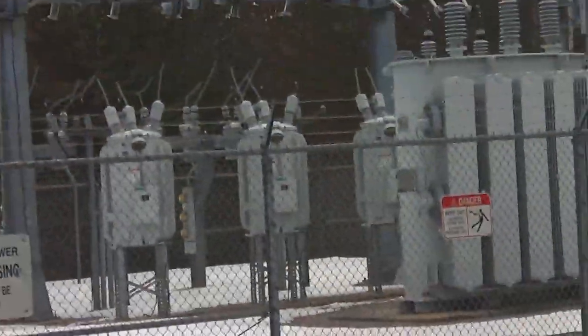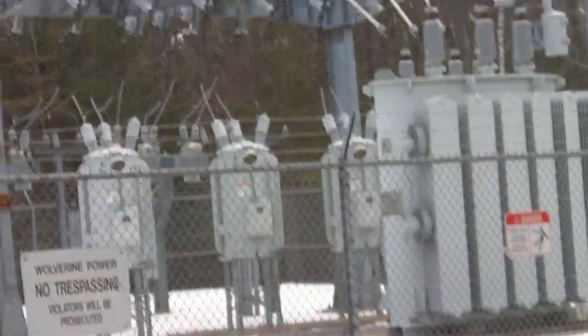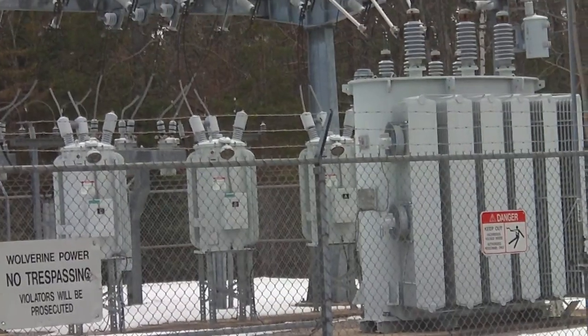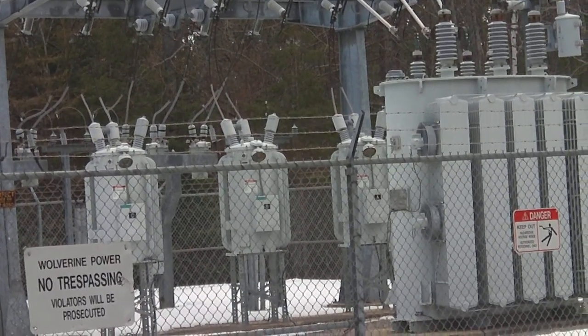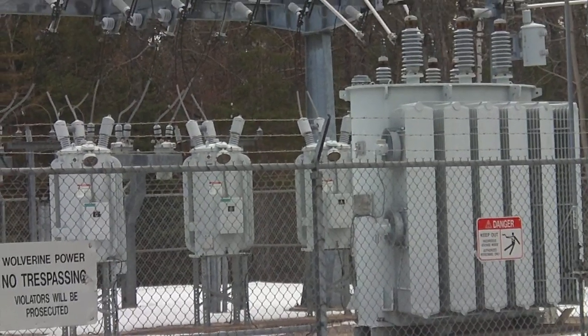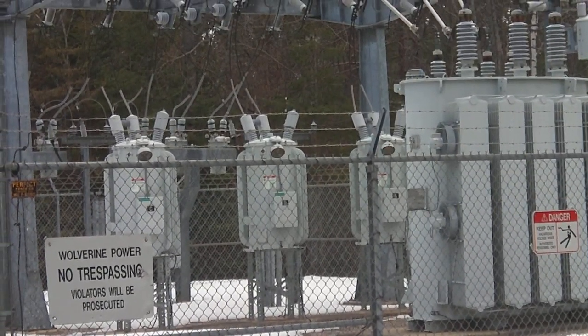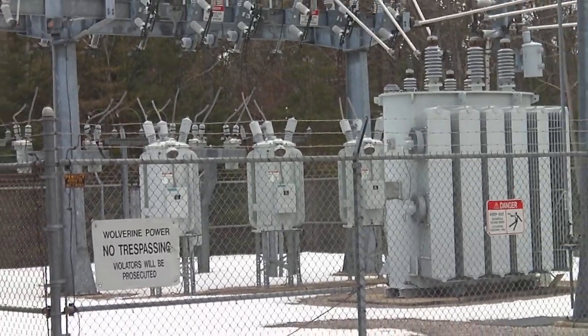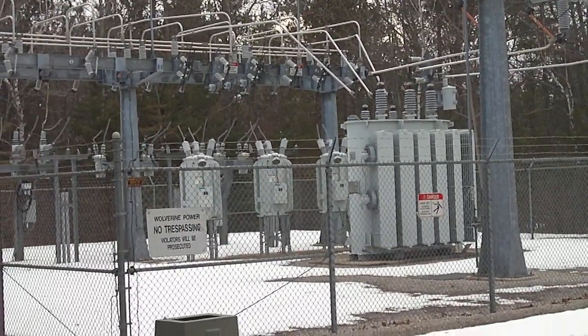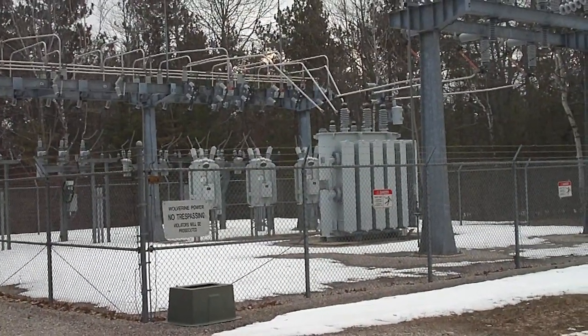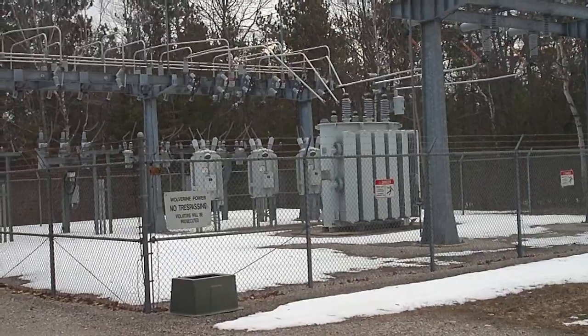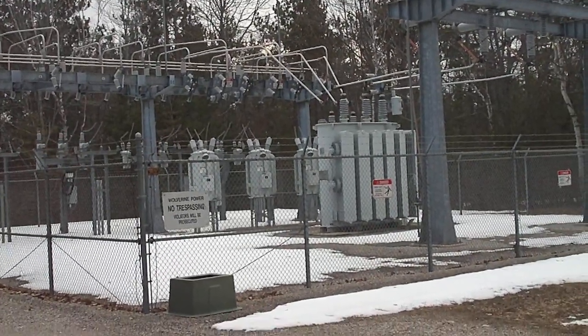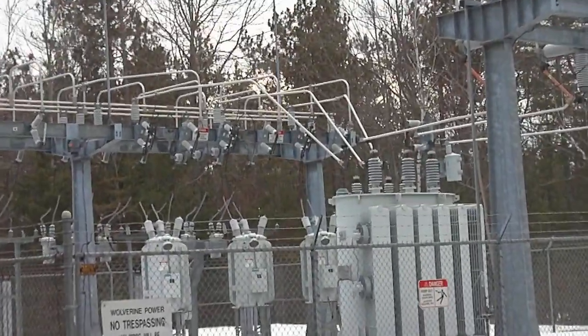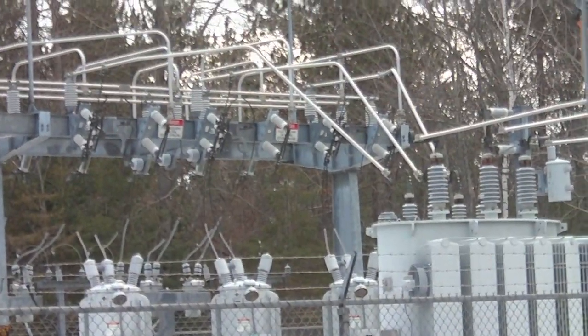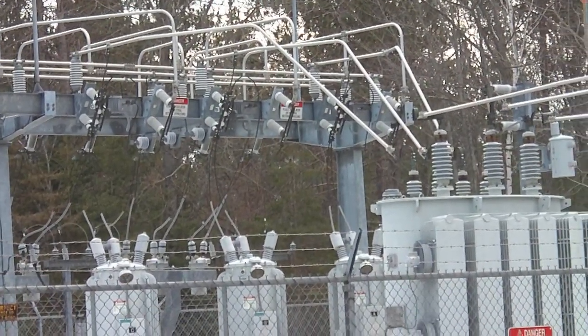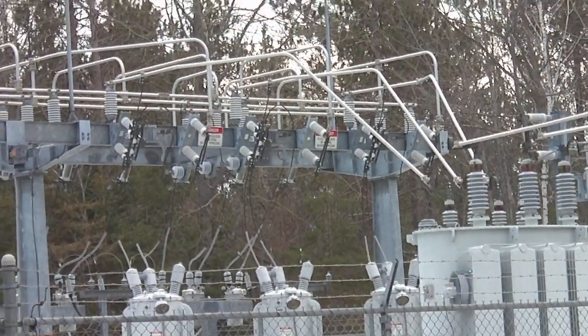The three units behind the power transformer are voltage regulators. You can tell by looking at the dial on them and the fact that they have three bushings on the top: the source, the load, and the source-load bushing. A lot of electric companies will put voltage regulators out in the field. Here with Presque Isle, they don't put them out in the field, they put them all in the substation. Alpena Power is a lot like that too. So those are your three voltage regulators, and if you look for those in the utility tech program, you can see the regulator bypass switches on the front side of that back steel superstructure.